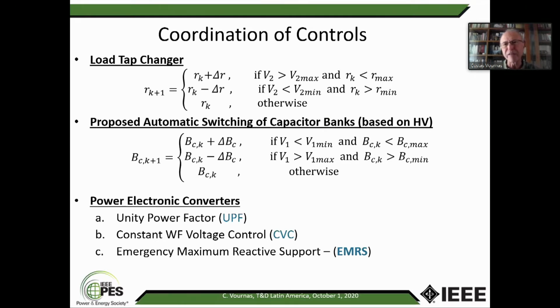concerning the reactive power. As I said, the active power control is such that all power coming from the wind is transmitted through the feeder. So the active power is already committed, but I have an opportunity to control the reactive power. And the 3 methods are, the most common, if you do not have any requests from the wind farms, is that they will operate at unity power factor, because in this sense they have the least current, thus the least losses on the feeder or the more revenue for the producer. So unity power factor is, let's say, the standard to start our discussion about reactive support.